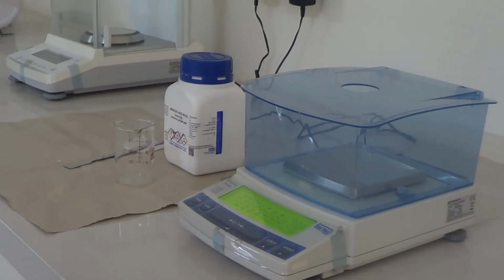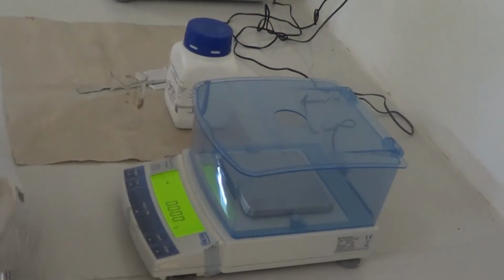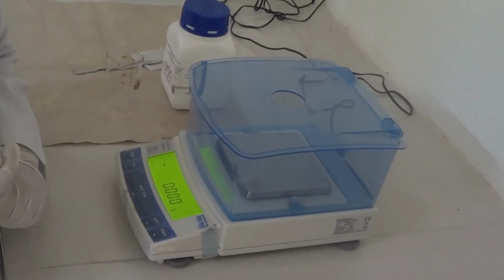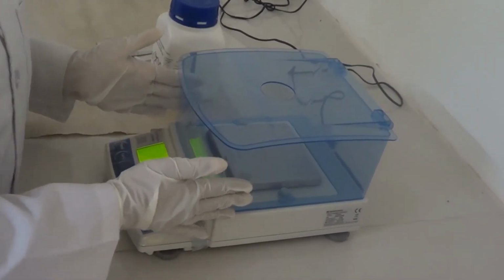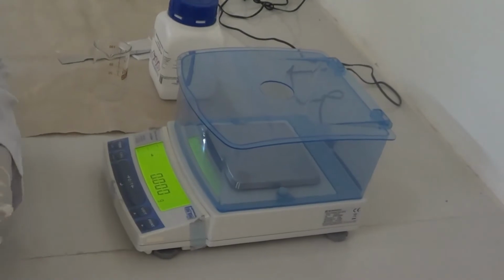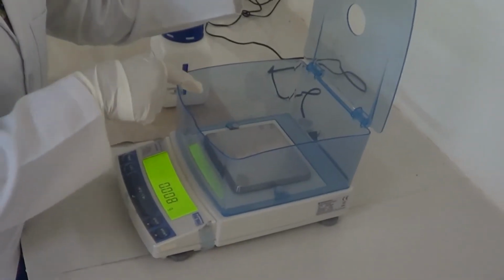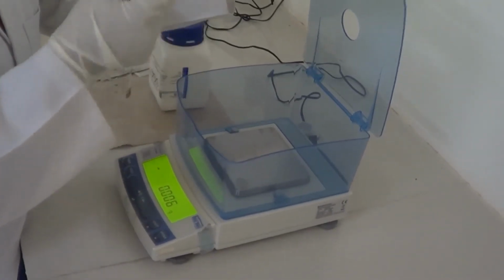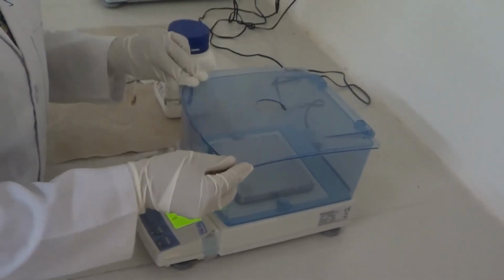It has a calibration range with external weights of 100 to 220 grams. It has a linearity of plus minus 0.002 grams. Now let's see the parts of balance. This is draft shield. It prevents air pressure to hamper the weighing. This is balance pan where we put the material which we have to weigh.